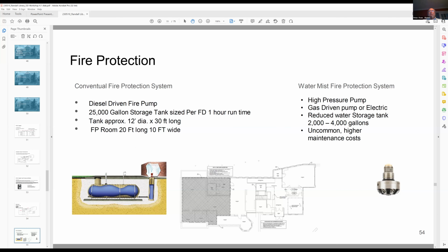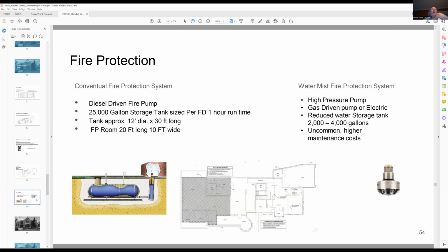And so as an alternative solution, there's a system called a water mist fire protection system. The difference between the two is under a conventional fire protection system, the water coming out is very large droplets, and it's basically coming out at a couple gallons per minute per head. And so it floods the entire building. If you've ever seen a sprinkler head go off, and it's not like the movies, it can be ultimately destructive to the environment. Once the fire goes out, they don't shut off until somebody manually shuts them off. Water mist systems are used typically in high value environments, such as collections, museums, data centers, and it does exactly what it says. It's a water mist system.